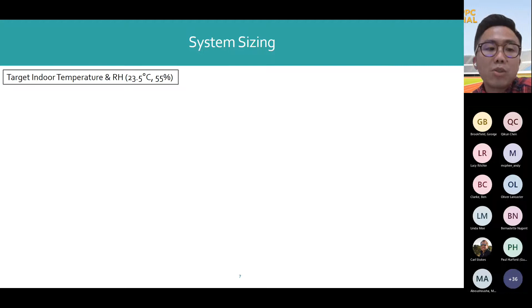After confirming with the consultant and client the achievable target indoor temperature and relative humidity to deliver the best thermal comfort to the occupants, I started with the solar thermal panel sizing based on the rooftop area. 65 solar panels is the maximum number of installation. Vacuum tube type panels were chosen because of their high efficiency.